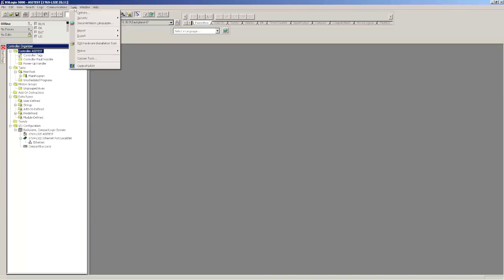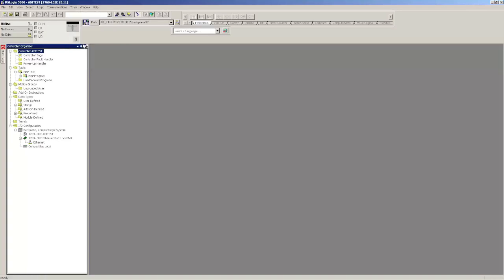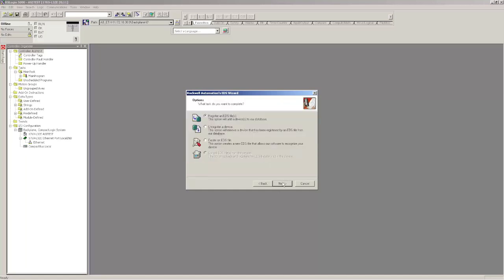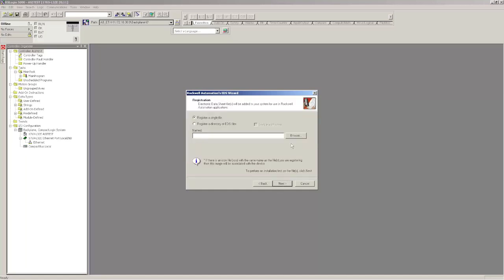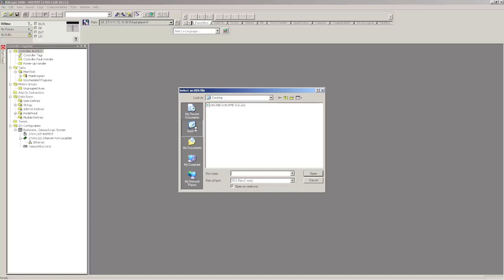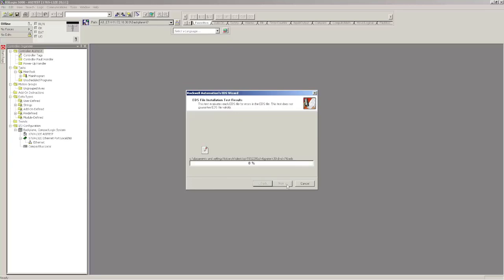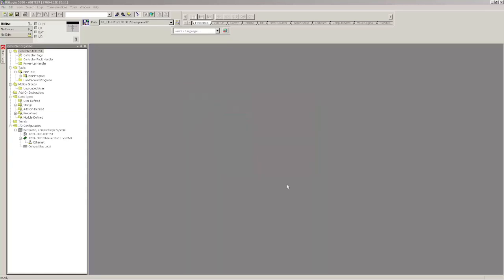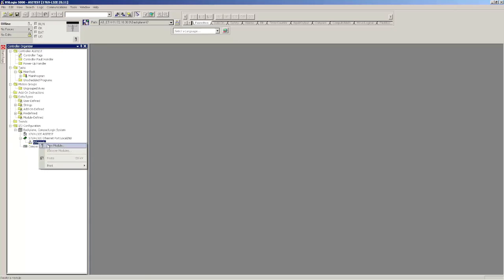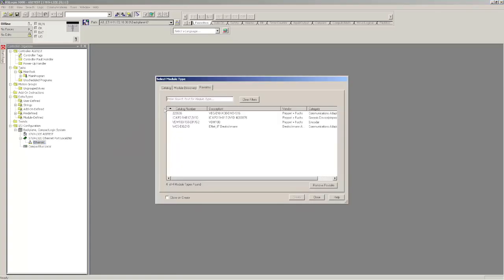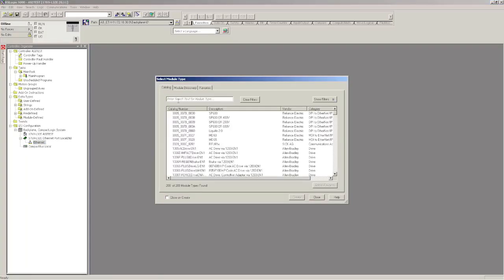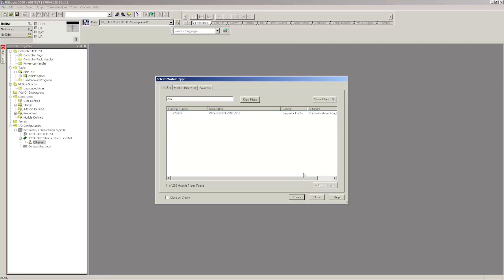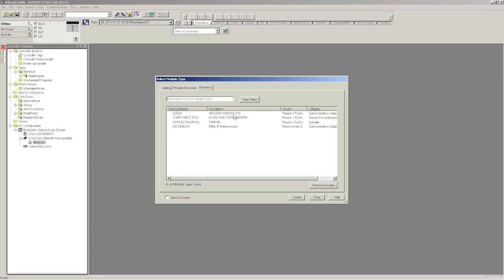So the first thing I want to do once the project is open is import the EDS file. It's the EDS tool. Go to Next, Register, Browse. It's on my desktop. That's the file I downloaded. Just choose Next a couple more times. It'll get that registered. Then choose Ethernet, New Module. When you're in the catalog section, you can just search VBG and it'll pop right up. This is the gateway that I chose before from the web. You can just choose Add to Favorites. That way, it's always in your Favorites menu next time you want to use it. Choose Create.